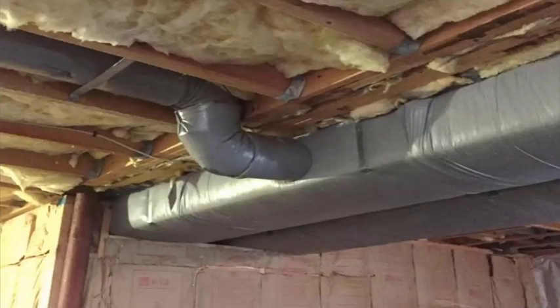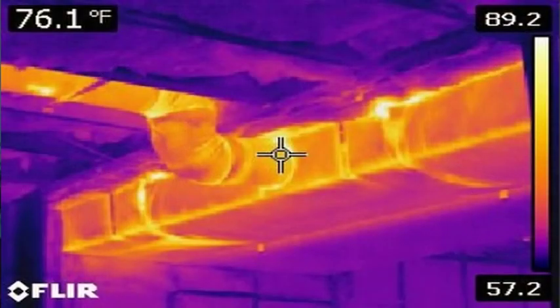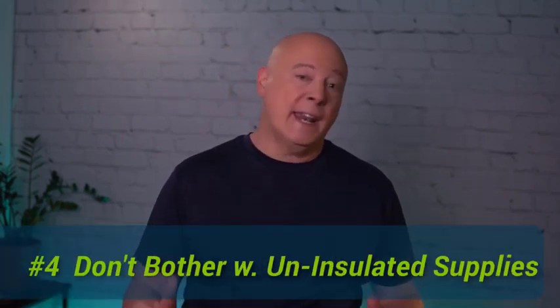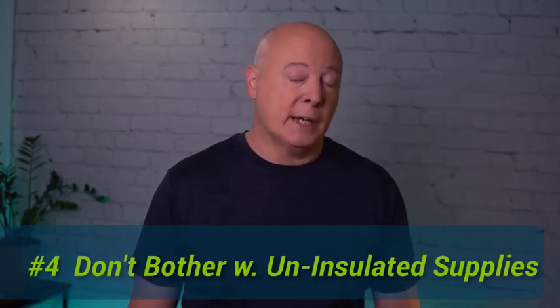Here's a shot of some wrapped leaky metal ducts near Boston. Notice that the entire jacket of the ductwork is glowing warm, not just where the leaks are. In this case, it happened very quickly after turning on the furnace, and I suspect it's because the escaping warm air is being pushed through the porous fiberglass. Since insulation performance depends on trapping still air, another benefit of duct sealing can sometimes be that you'll restore lost R value as well.